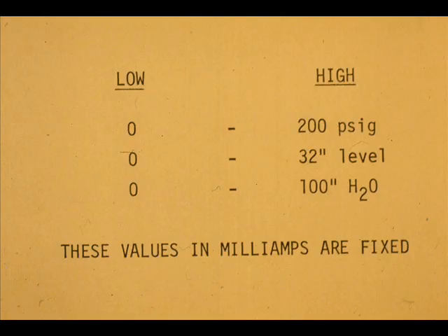It makes no difference whether the input range happens to be 0 to 200 PSIG, 0 to 32 inches level, or 0 to 100 inches of water. The low and high end of the range outputs in milliamps are set by the milliamp output range of the specific transmitter.